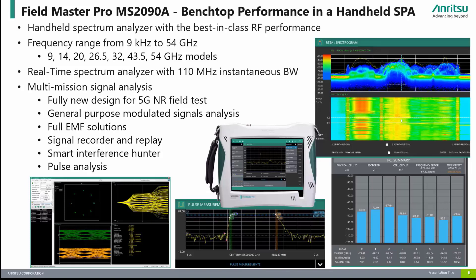The Fieldmaster Pro MS-2090A is Anritsu's premium handheld spectrum analyzer with advanced features previously only seen in much more expensive benchtop instruments. The MS-2090A frequency range starts from 9 kHz at the low end and has various frequency options starting at 9 GHz all the way up to 54 GHz. Key features include real-time spectrum analysis with up to 110 MHz instantaneous bandwidth, display average noise level of minus 164 dBm, third-order intercept of plus 20 dBm, and plus or minus 0.5 dB typical amplitude accuracy.